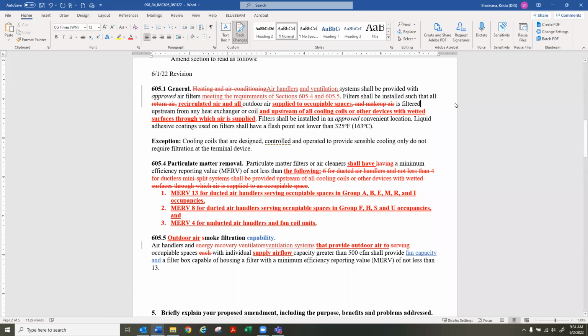It's an interesting distinction. You could have an ERV, for example, that dumps outdoor air into a dwelling unit. And as long as it's not integrated with the air handler, as long as the air handler had a MERV 13 filter, that outdoor air would be filtered prior to being introduced into the heat exchanger or coil. So if you broke it up as proposed, there might be some confusion about whether you would have to do double filtration in that case and filter the outdoor air for your separate dedicated system and then also filter the recirculated air, or if you just need to filter it before it goes through the heating and cooling air handler. Yeah, that's a good point.